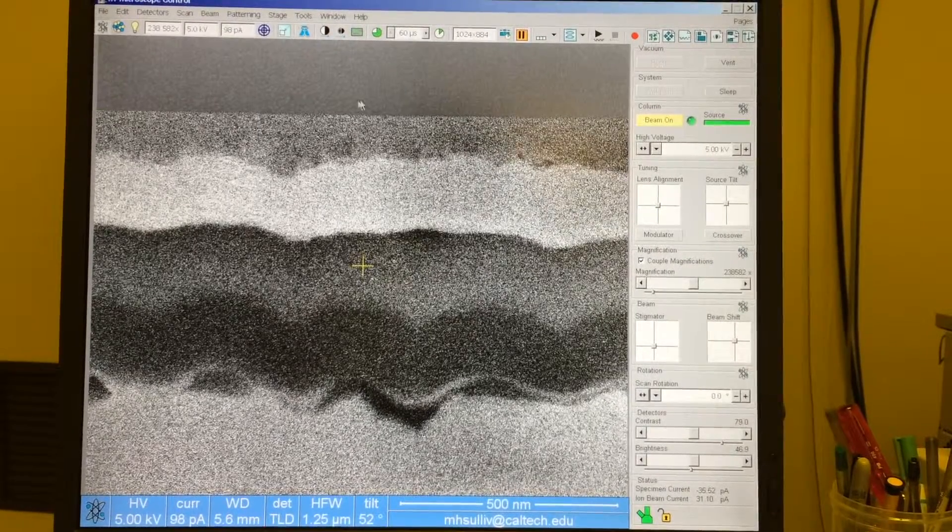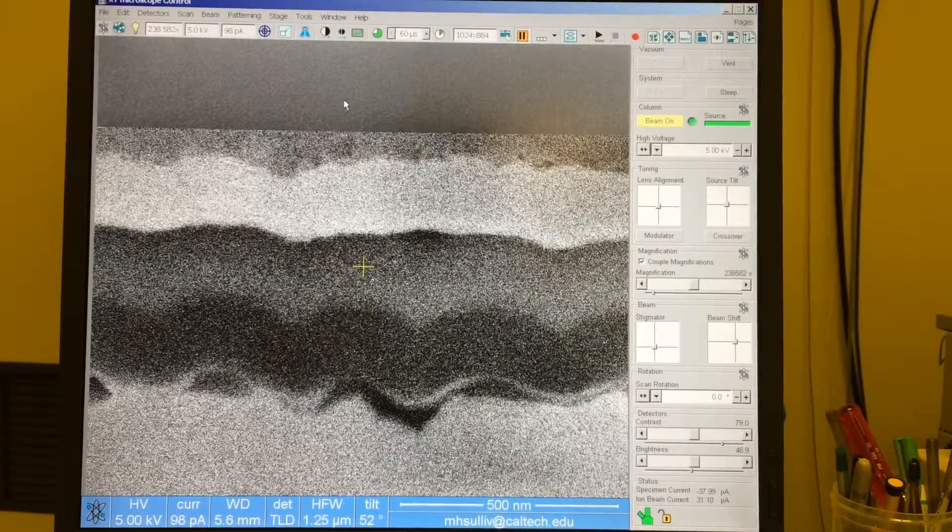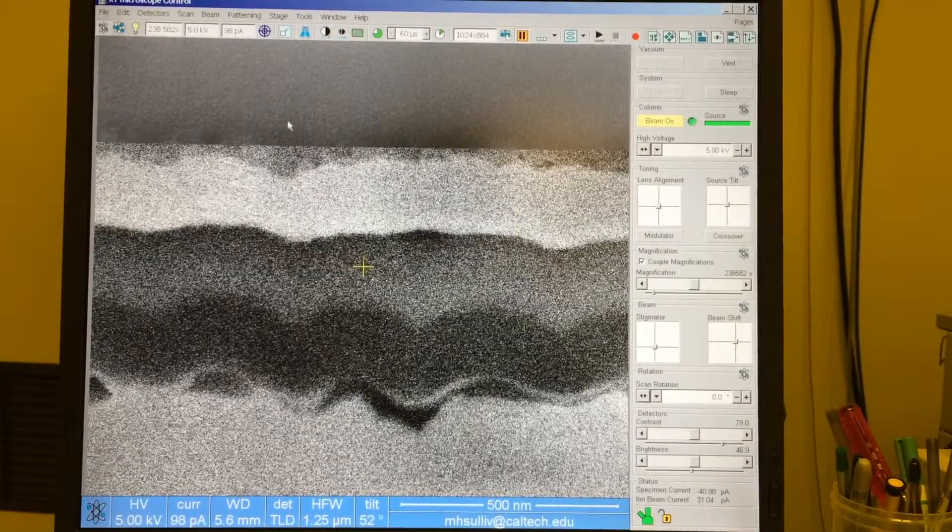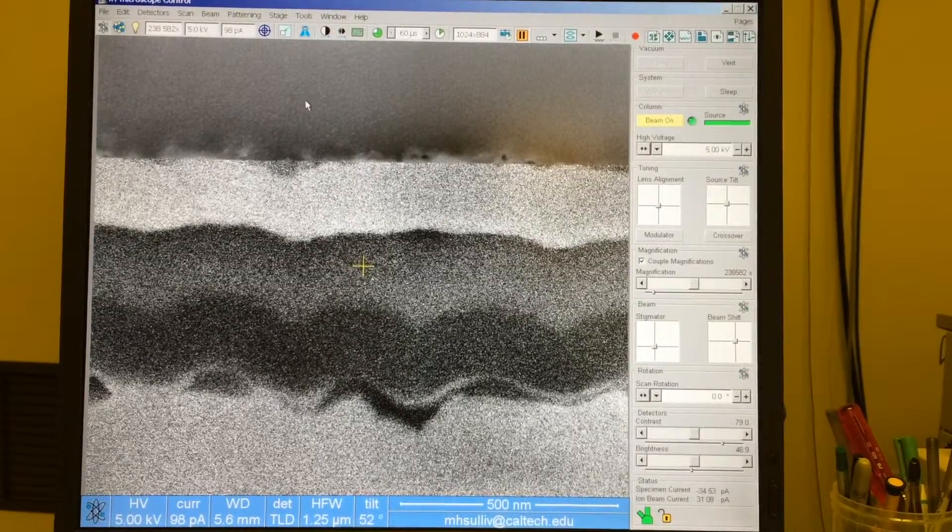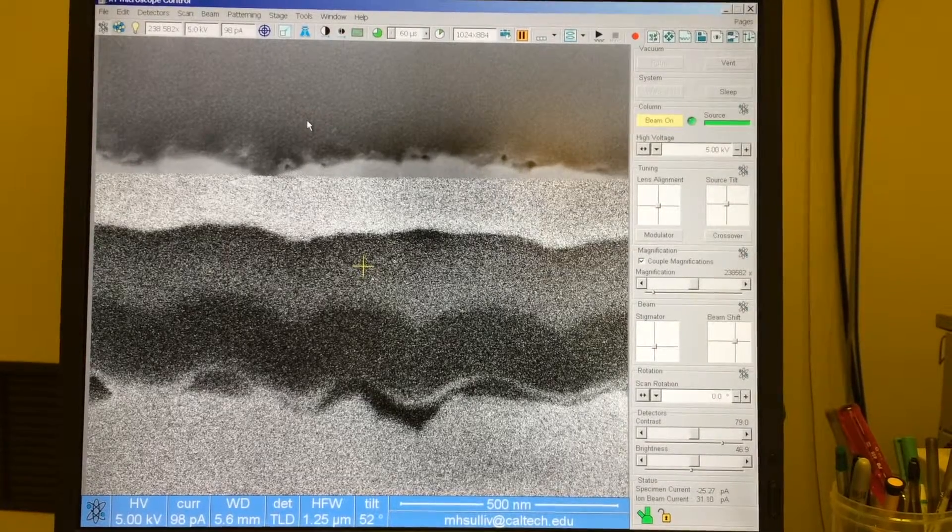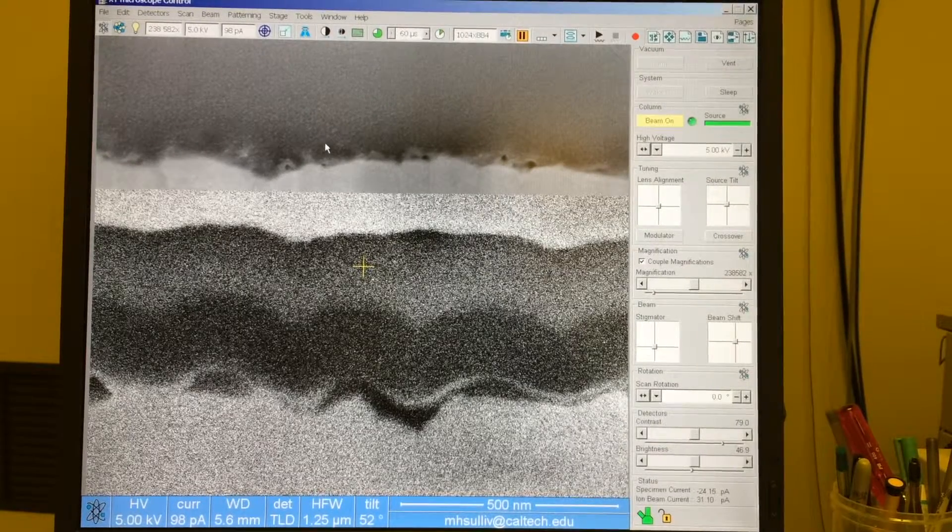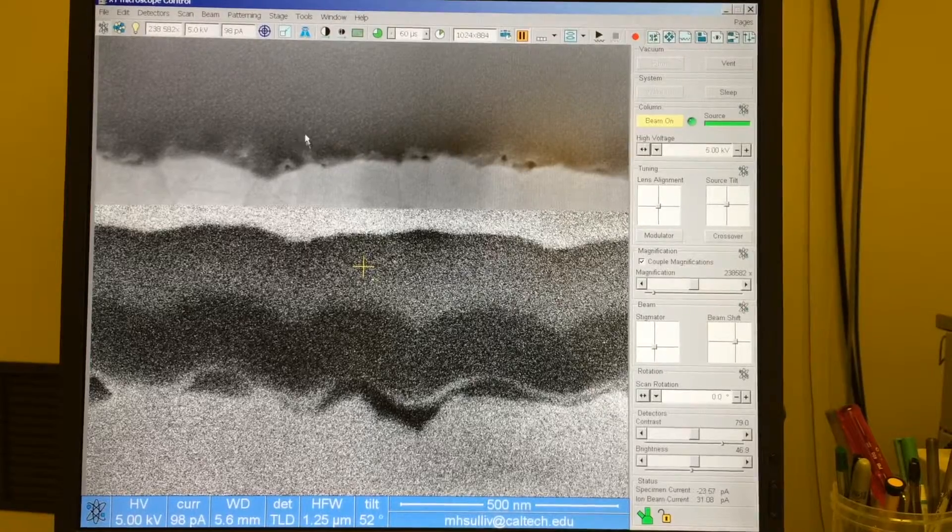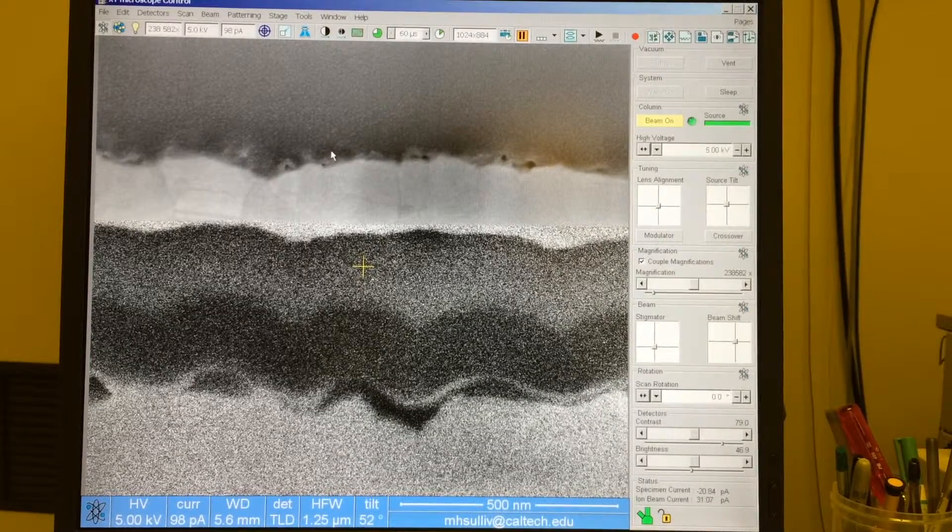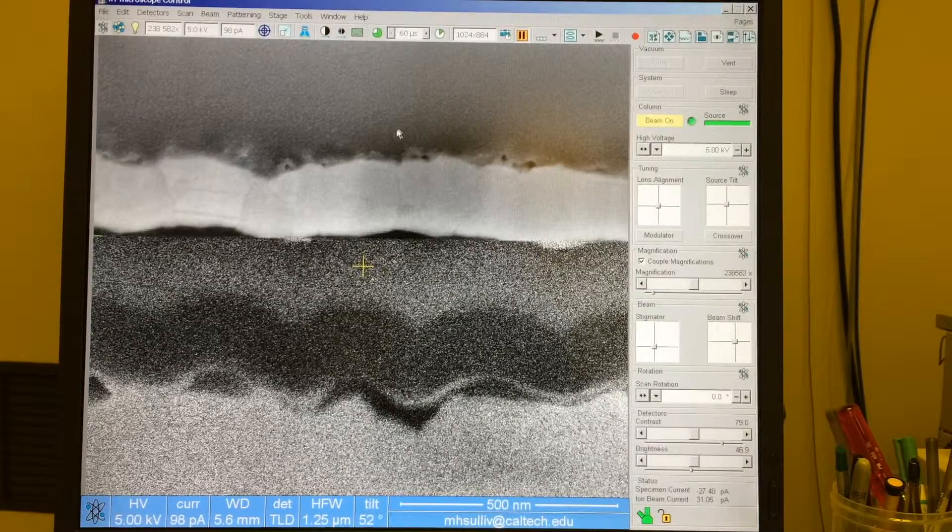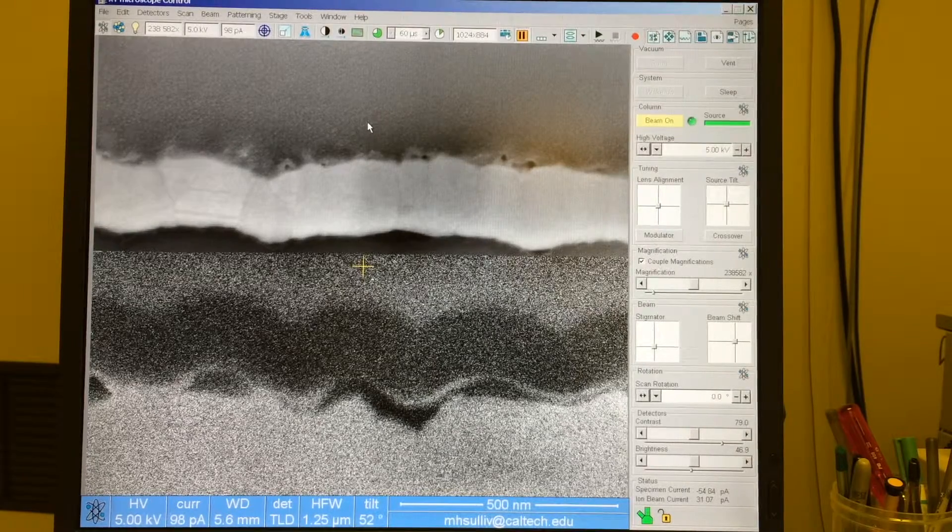This will make it pause when it gets to the end of the image, and we'll save it that way. So as we're scanning here, one thing we can see is there's some texture here. And this is the electron beam deposited platinum layer, and there are nano-sized grains in it. So if we can see that nano texture, then we know that we've done a good job with the alignment. So look for that after you've finished your alignment.